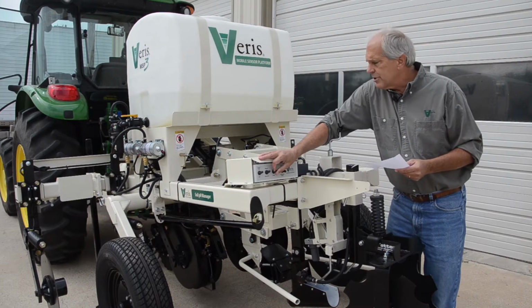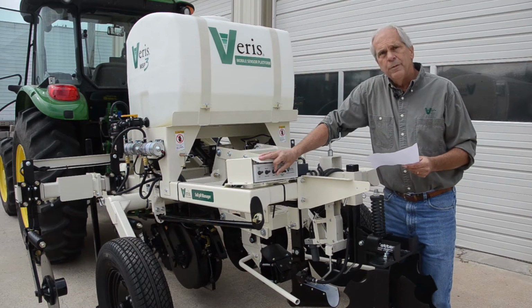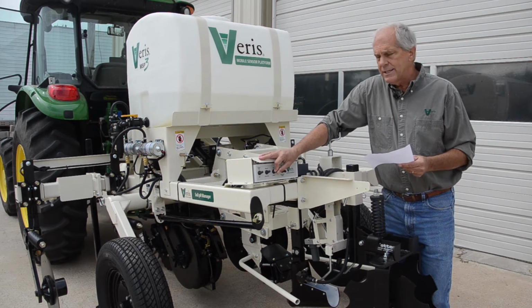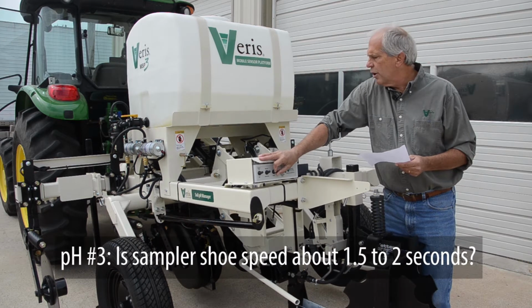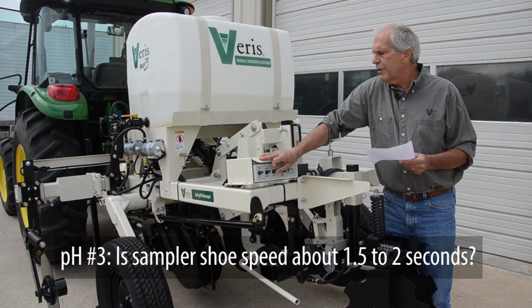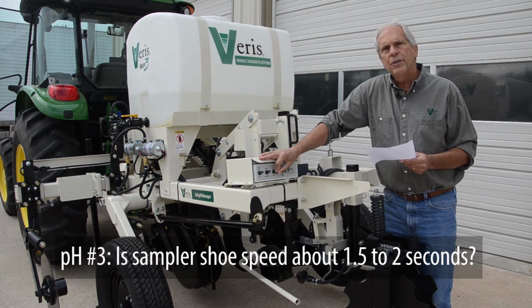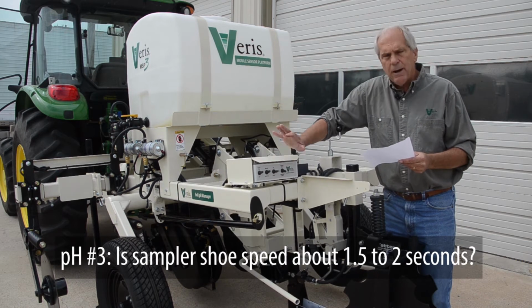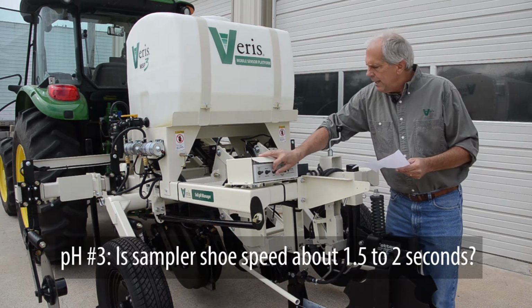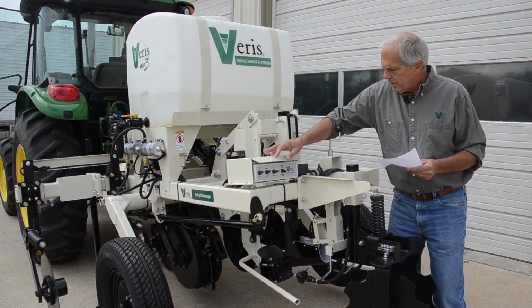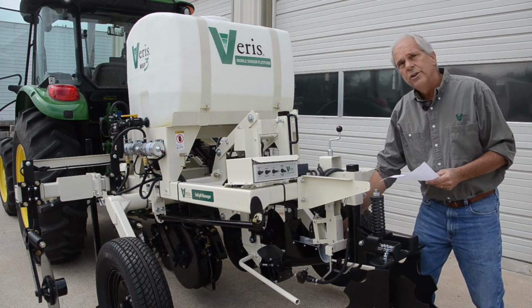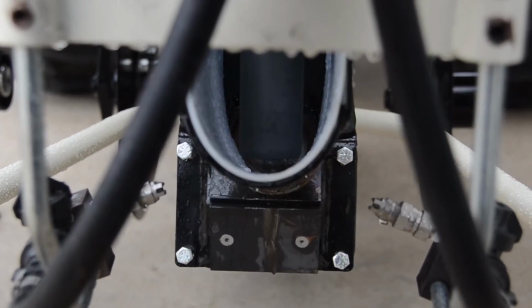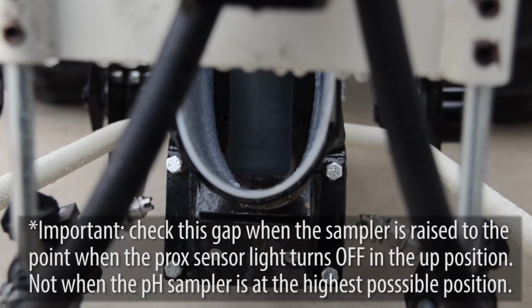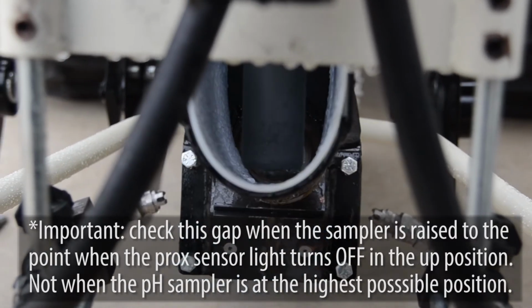Third item is the sampler shoe movement, about 1.5 to 2 seconds — that's about the right speed. One thousand one, one thousand two — about 2 seconds. Next, check the electrode gap: when the shoe is all the way raised, do we have the proper electrode gap between the electrodes underneath here and the pH sampler shoe?